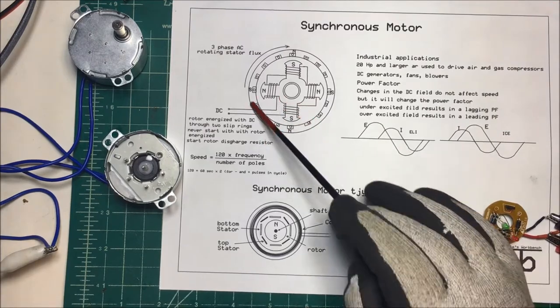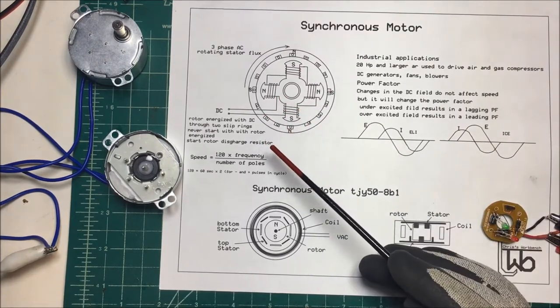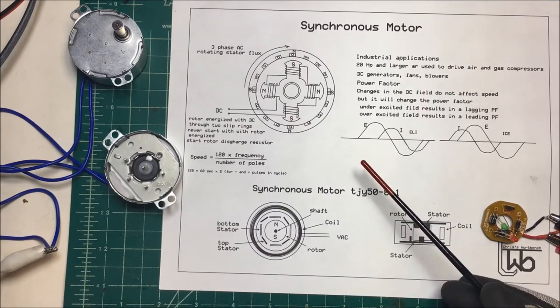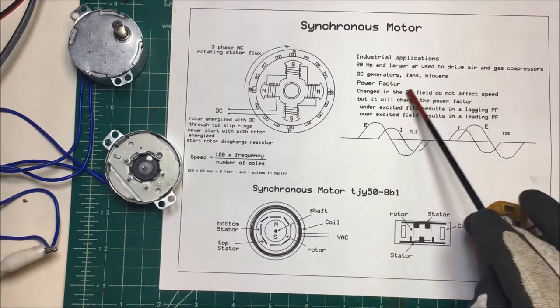It serves two purposes: you need the blower, you need the fans running anyway, and by using a synchronous motor you can correct the power factor. That's why they use these a lot in industrial applications.